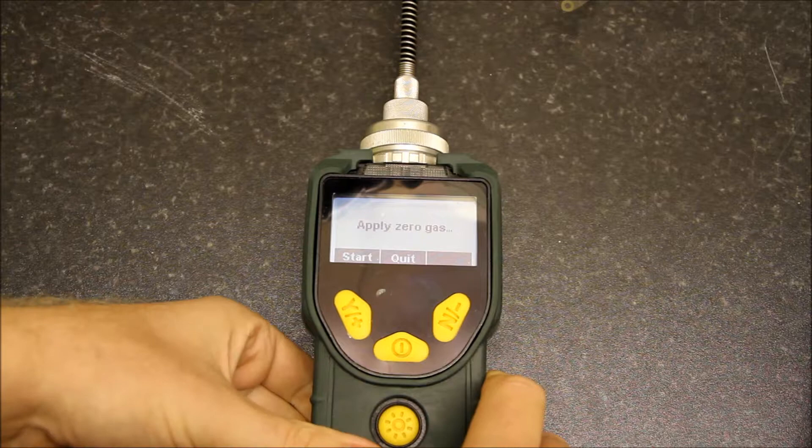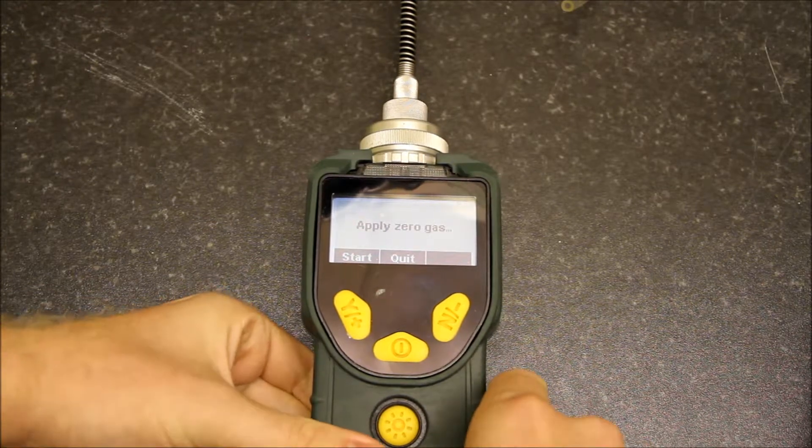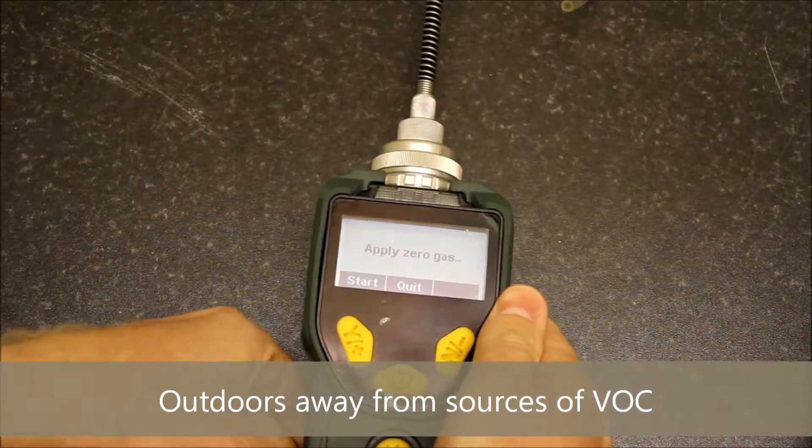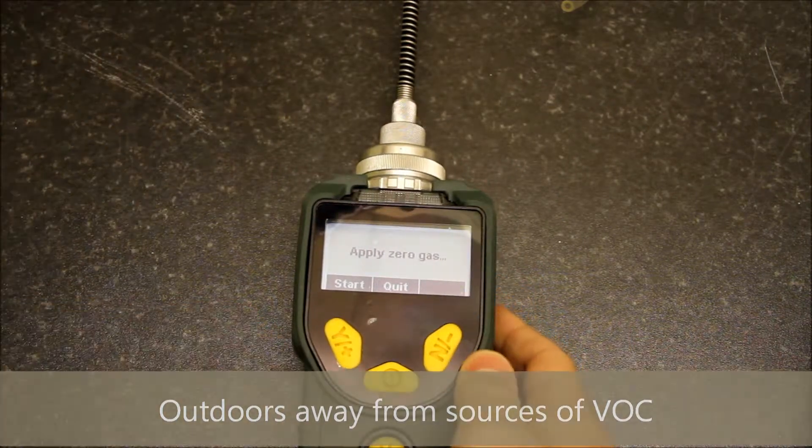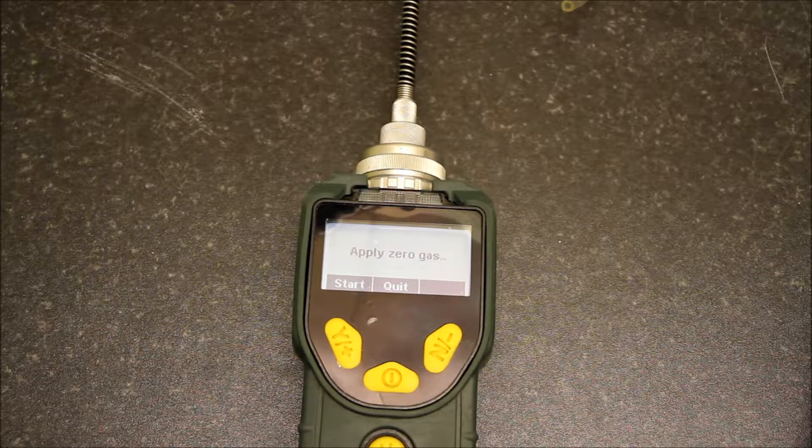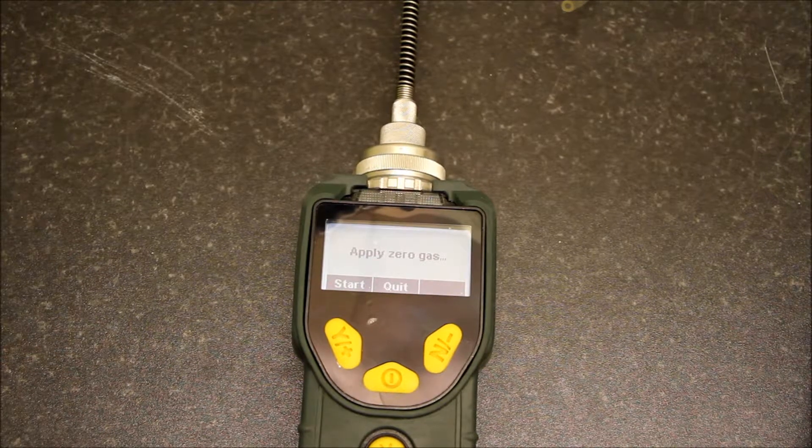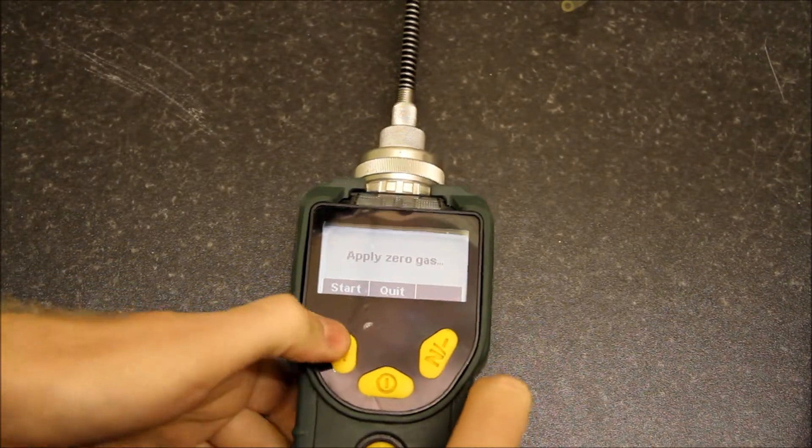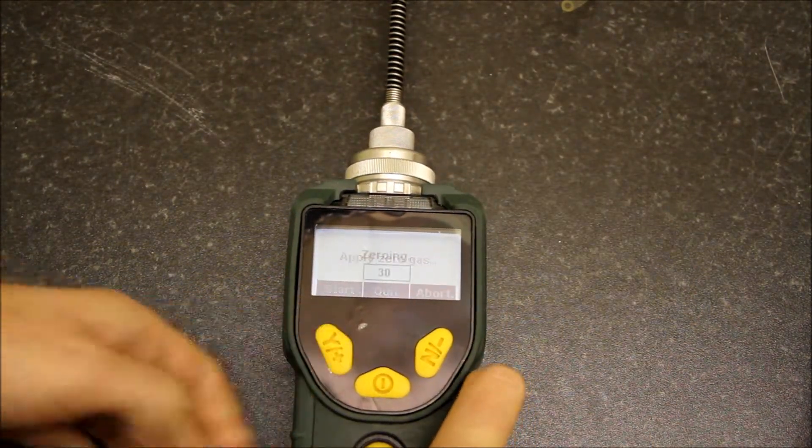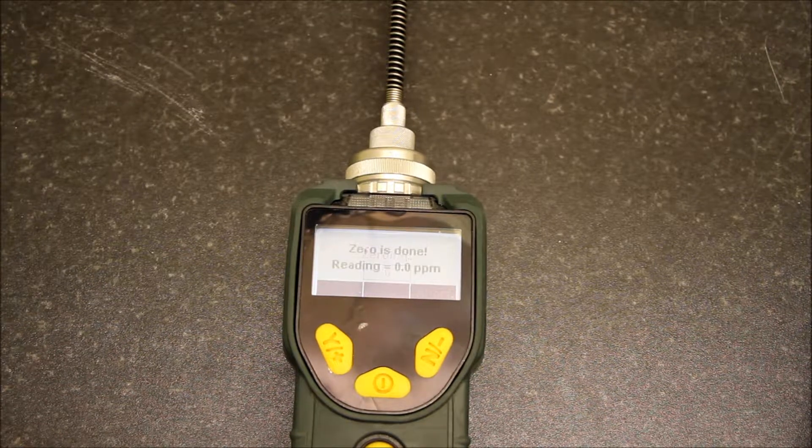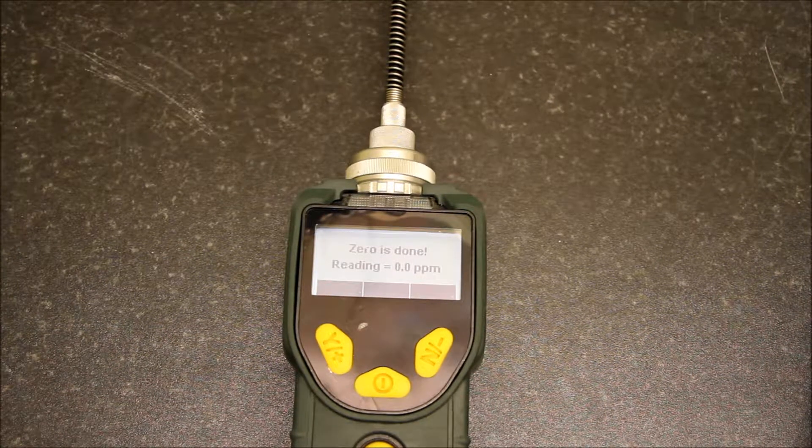The best place is outside. Outside has very low ambient levels of VOCs, such that on this version of the monitor you're unlikely to see anything with the resolution of 0.1 ppm. Assume we're outside now. We just press start and this will now zero for 30 seconds.